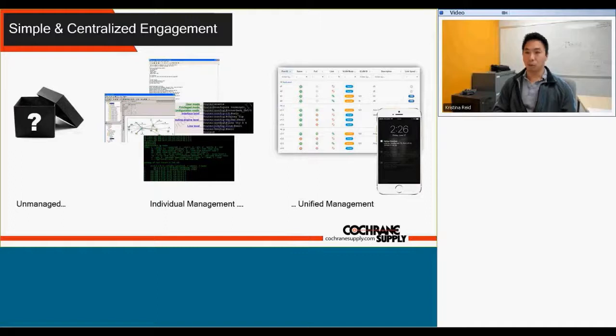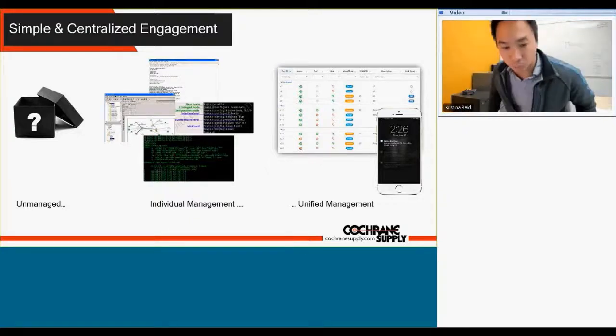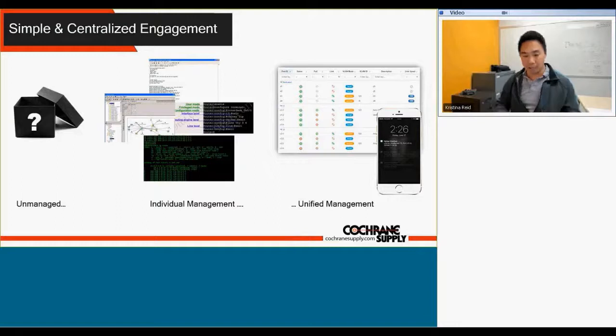If you go to Best Buy and bought a cheap switch, you will likely get an unmanaged switch. An unmanaged switch will work, but when it doesn't, you have no clue where it went wrong. In today's world, where cybersecurity is a very big deal, and convergence is one of the biggest trends - actually no longer a trend, it's a reality - you have a network that connects HVAC, lighting, maybe multiple HVAC vendors, energy, parking systems, whatever you want. You need to separate each service, each vendor, and sometimes each building or each floor. So you need to go into a managed switch environment.